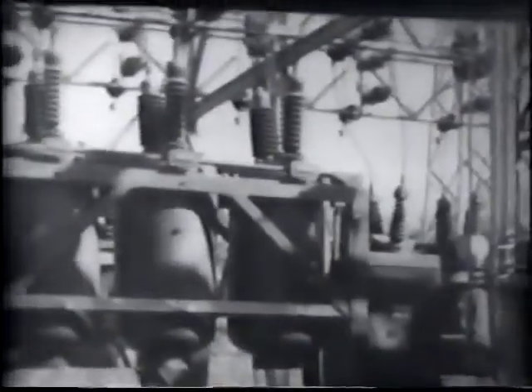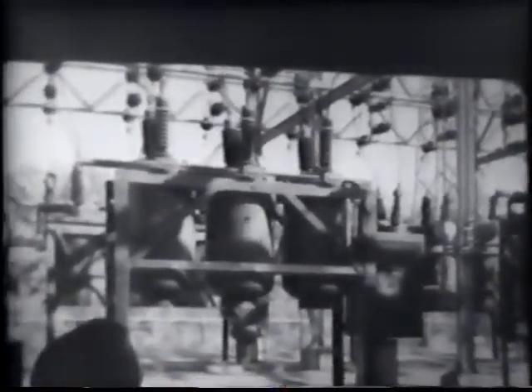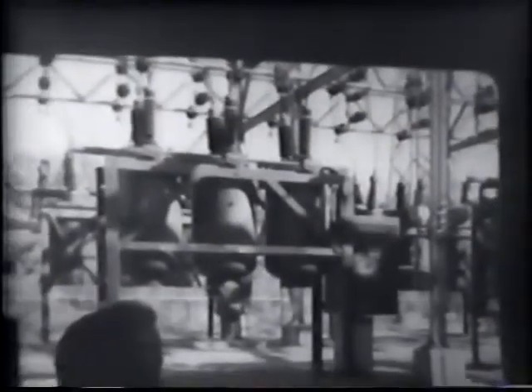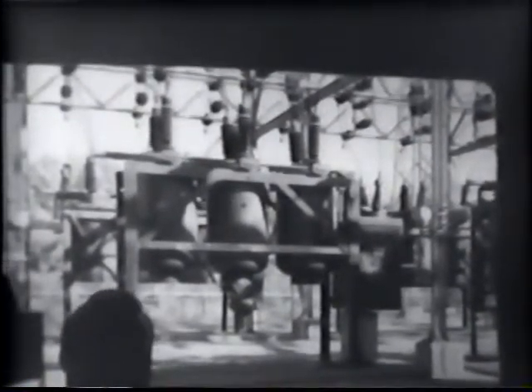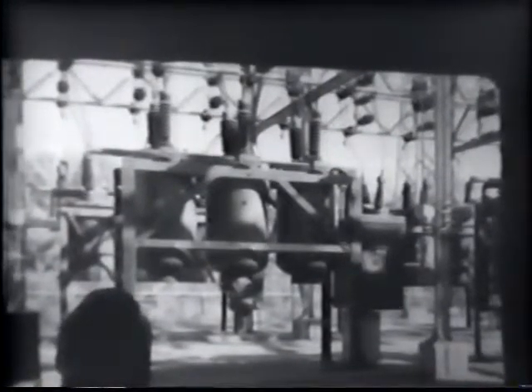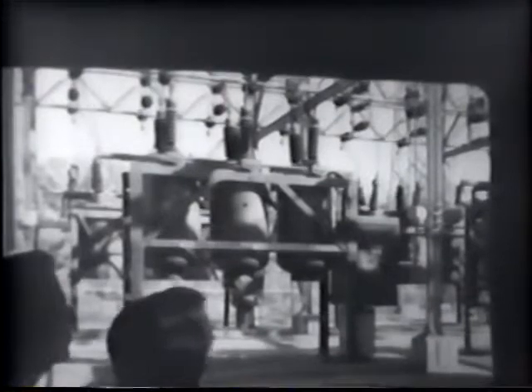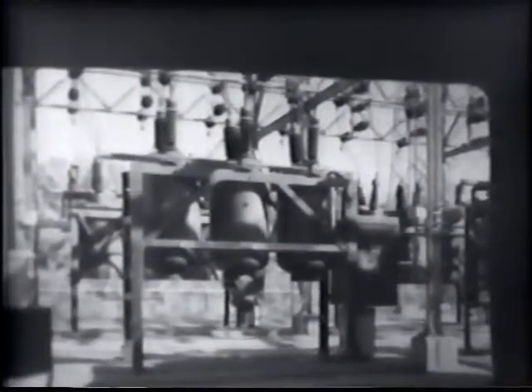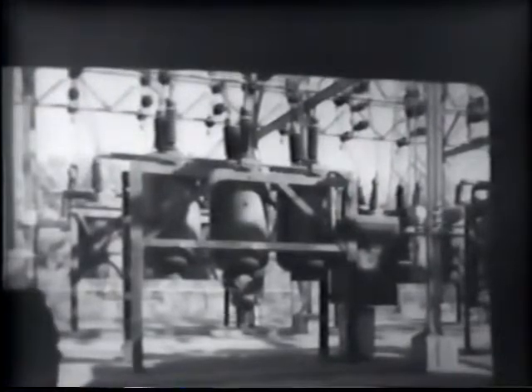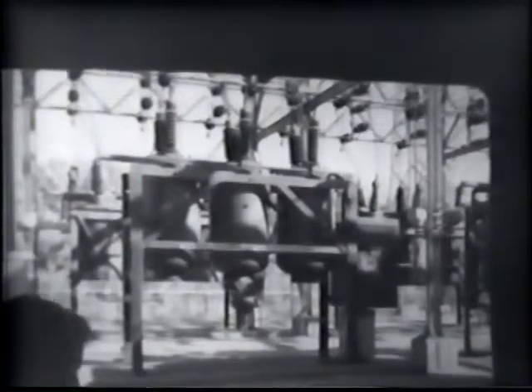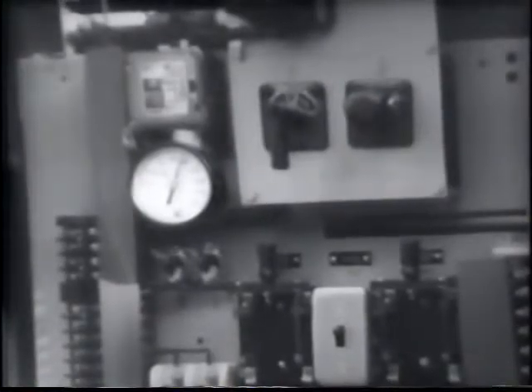Another type of 69 kV 3-tank circuit breaker. This I think is an Allis-Chalmers. This particular view here doesn't house too much. It's different from the G04B. It's included here because it has a different type of operating mechanism. This happens to be a compressed air operated mechanism. This is the air storage tank up here, the air compressor motor, some of the controls here for the pneumatic air piping. And this shows some of the control wiring for the circuit breaker.